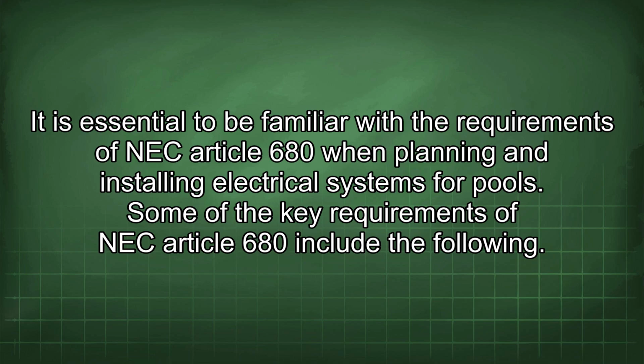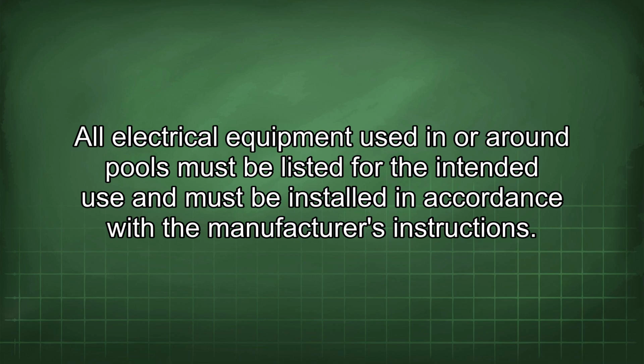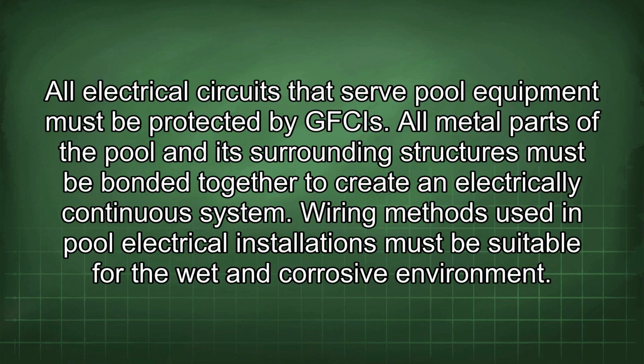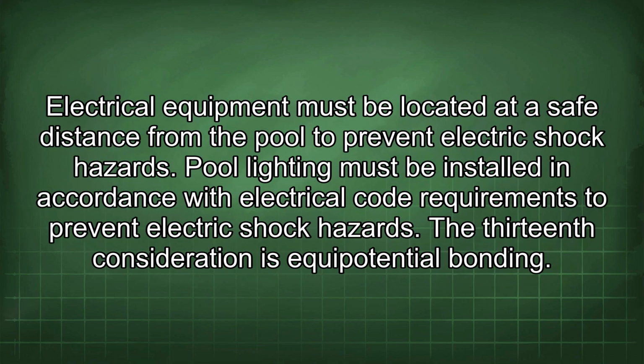Some of the key requirements of NEC Article 680 include the following. All electrical equipment used in or around pools must be listed for the intended use and must be installed in accordance with the manufacturer's instructions. All electrical circuits that serve pool equipment must be protected by GFCIs. All metal parts of the pool and its surrounding structures must be bonded together to create an electrically continuous system. Wiring methods used in pool electrical installations must be suitable for the wet and corrosive environment. Electrical equipment must be located at a safe distance from the pool to prevent electric shock hazards. Pool lighting must be installed in accordance with electrical code requirements to prevent electric shock hazards.